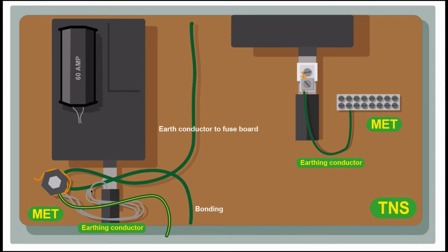But you've got to take good care here. This is quite a stiff wire that comes, it's soldered onto the supply cable. If you've got quite a nice long length of that, and you can remove that safely without putting any pressure or strain on the soldered joint, I'm quite happy to do that. But if you've got any doubt, if it looks old and dodgy, don't bother. Call the DNO and tell them to come in and reconnect your earth. But if you're not going to put any pressure or strain on the connection, I'm quite happy to undo this and re-terminate it in an earth bar like this, and then we can easily take our ZE reading because it's all disconnected.